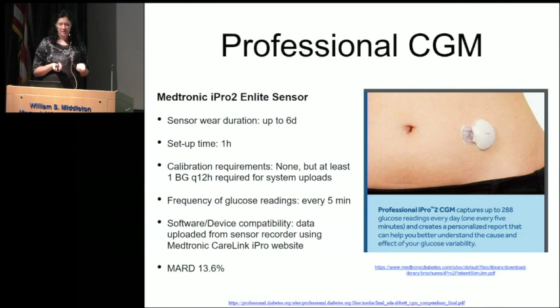The difference between the Medtronic and the Freestyle Libre is that the Medtronic is a continuous CGM, and so it's continually collecting data, and if there was a reader available, the patient would be able to monitor that, as opposed to a Flash CGM, which is the Freestyle Libre. It requires the patient to scan the device in order to see what the glucose reading is. The MARD for the Medtronic iPro 2 is 13.6%.